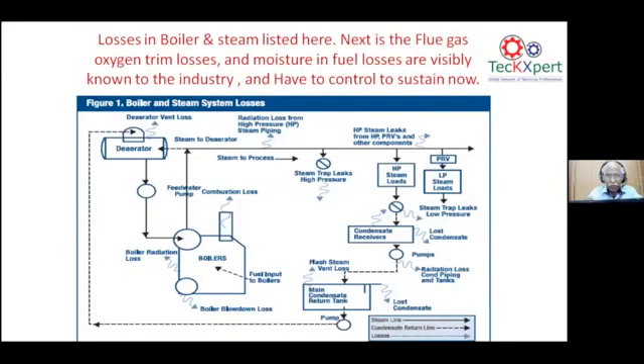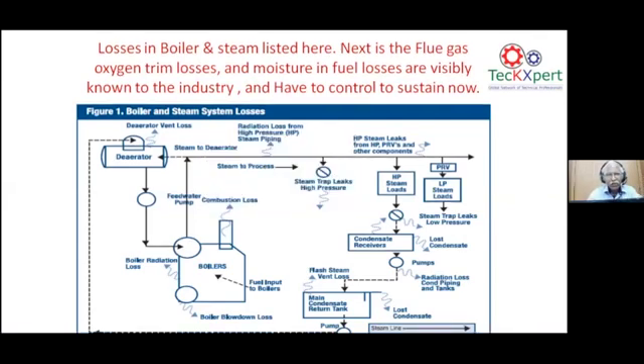Coming to the boilers, a list of losses are there. More than 10 to 12 losses are there. Apart from the losses on the feed water tank, the radiation loss, the one on the piping, then the boiler loss, radiation loss, the low flash steam loss, the high HP steam loss, the flue gas loss, and the moisture in the fuel. These are all the areas where it can definitely be seen.